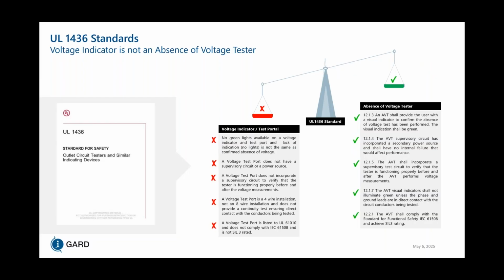So in having these requirements stipulated in UL 1436 and comparing them with respect to the voltage indicator and the test port to the absence of voltage tester, we can see that the voltage indicator and test port is not meeting some of these requirements, particularly with respect to voltage pickup, and it doesn't have a supervisory circuit, and it's usually not complying with IEC 61508 and is not an SIL3 rated device. Voltage test ports are typically rated to UL 61010.